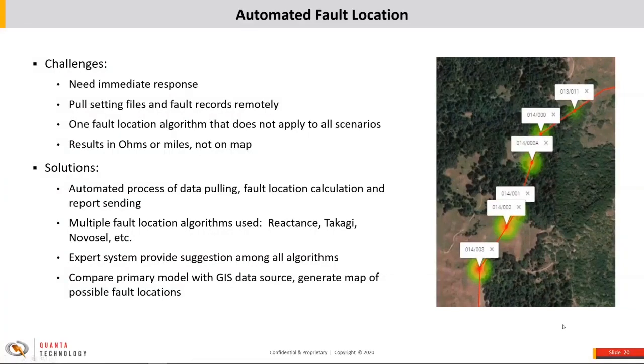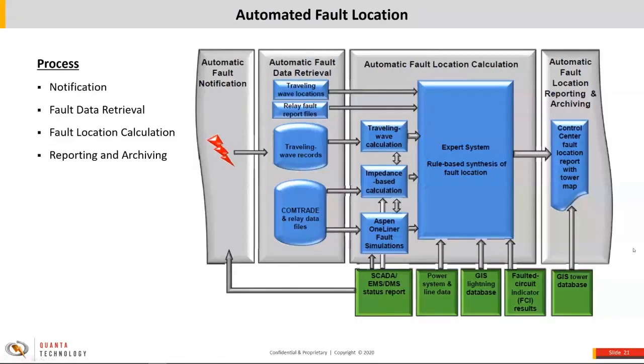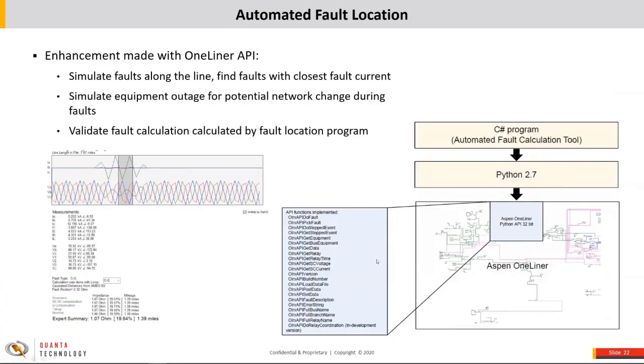Since the program is connected to a GIS data source, it can automatically draw the fault on the map. The bottom circle is the largest and the circles go smaller toward the top, meaning it's more probable for the fault to be near that tower location. In the center of the process, the expert system is connected to one-liner. Once it does all internal fault calculations, it calls one-liner API functions to simulate the fault and compare the fault currents and voltages with what's calculated within the expert system to further validate the results.